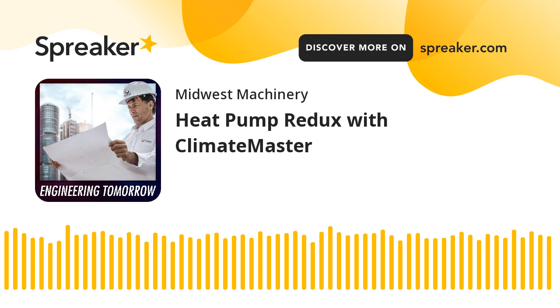Now, first up, what we have is vertical closed loops. Vertical closed loops use boreholes drilled to an average depth of about 250 feet. Once the loop pipe is inserted in the bore, it is grouted for maximum thermal conductivity. When space is limited on site, vertical loops are the most common type of geothermal loop installed.